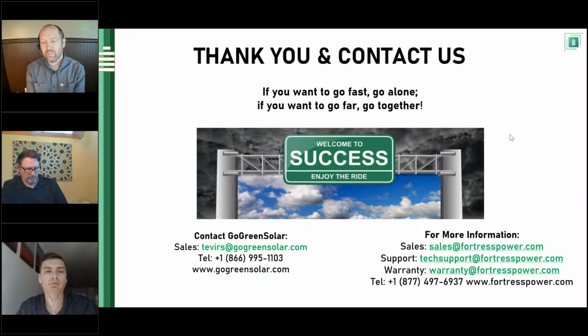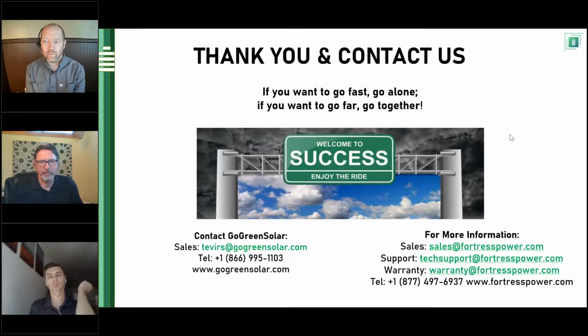But minimum, I can address real fast. Basically, the spec sheet is just going to show you the max discharge and max charge rate per battery, and once you parallel those, they add up. For example, if it was 50 amps and you had three of them, now you can charge at 150 amps. Most of the time, when you look at the wattage of the array and divide by the nominal DC voltage or the charge rate of the inverter, you're not going to run into any limitations with three or more in most scenarios, unless you have a whole pile of inverters, but it's pretty easy to figure out.